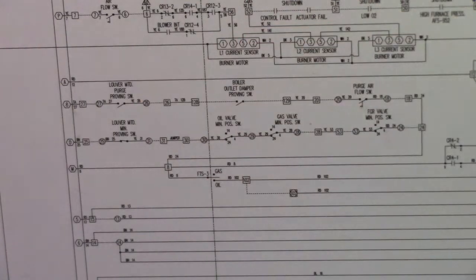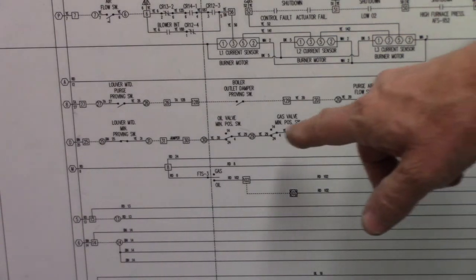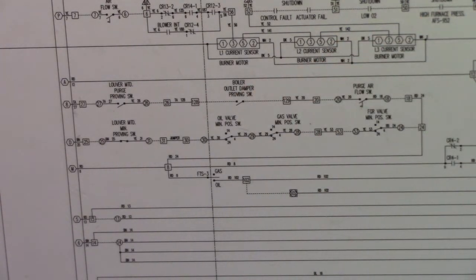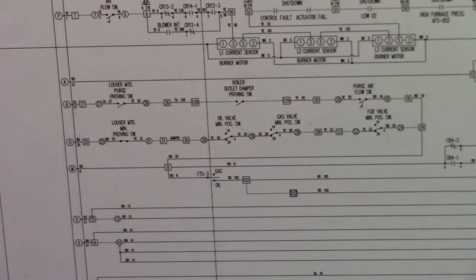All three of these need to be in proper position for a purge to occur. The outlet damper needs to be open, we have to have enough purge air for the purge, and the inlet damper needs to be open.